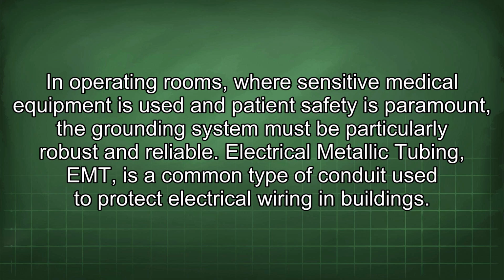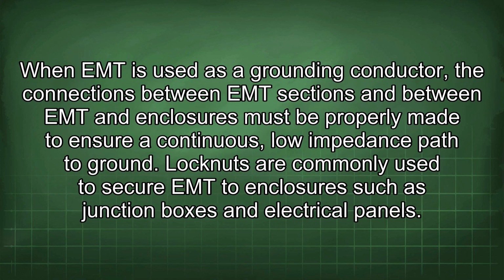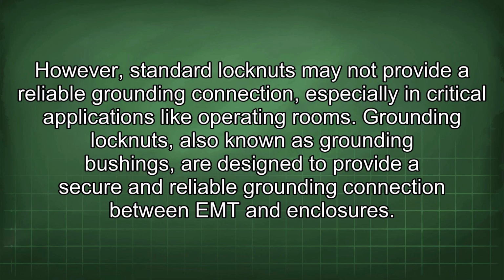robust and reliable. Electrical metallic tubing (EMT) is a common type of conduit used to protect electrical wiring in buildings. When EMT is used as a grounding conductor, the connections between EMT sections and between EMT and enclosures must be properly made to ensure a continuous, low-impedance path to ground. Locknuts are commonly used to secure EMT to enclosures such as junction boxes and electrical panels. However, standard locknuts may not provide a reliable grounding connection, especially in critical applications like operating rooms.